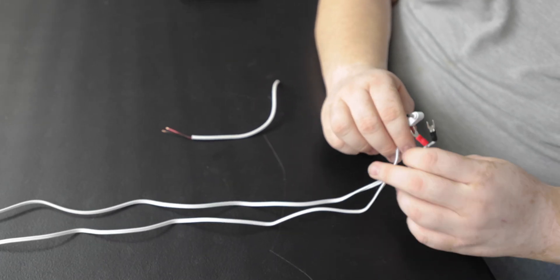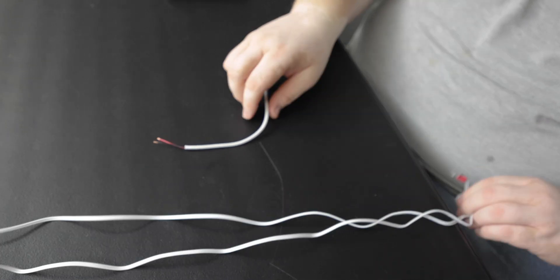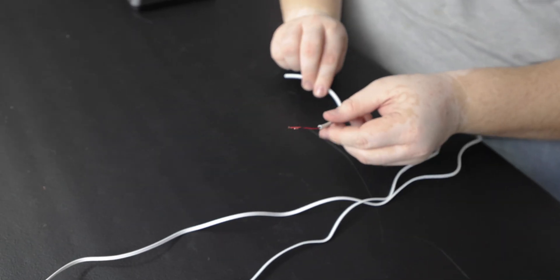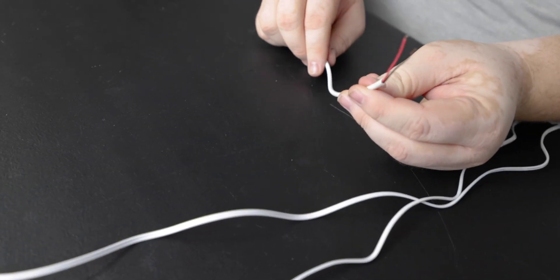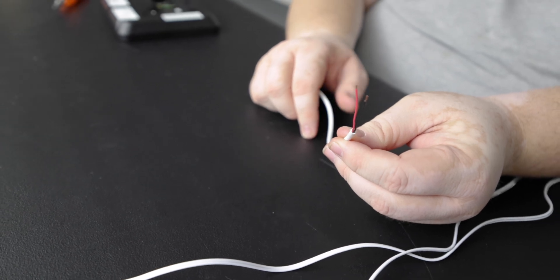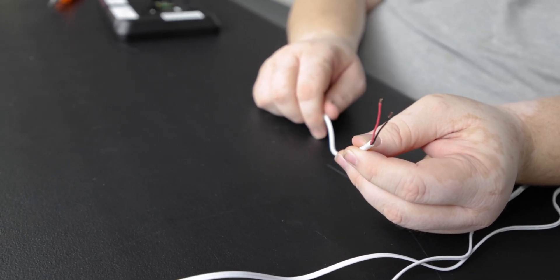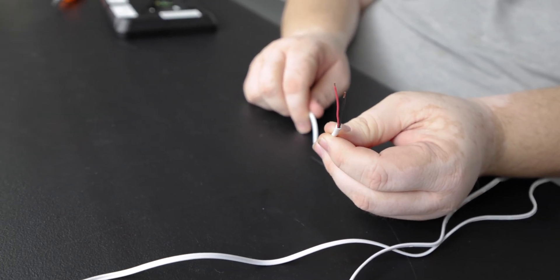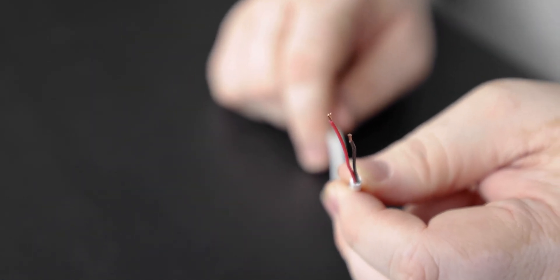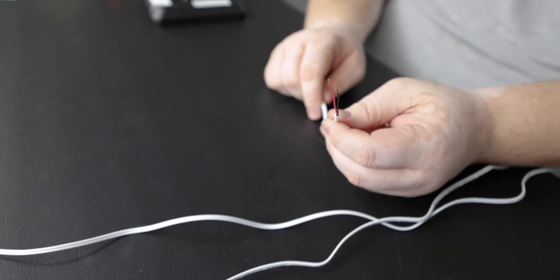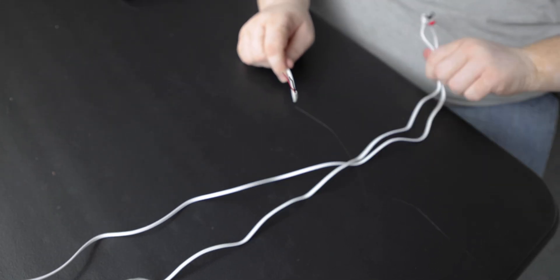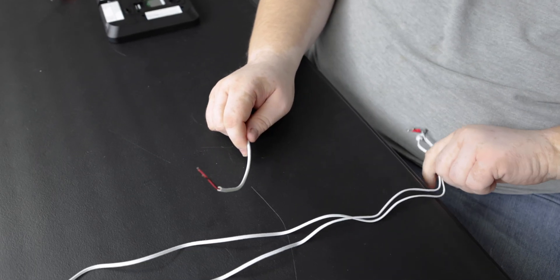But if you need to go further than eight feet, the recommended wire size is 18-gauge stranded because 18-gauge is what fits into the connections for the wires. The LT cable does not fit into the IQ4 connections. So if you're not going to go very far, there's no need for the LT cable because you've got the cable that comes with it.